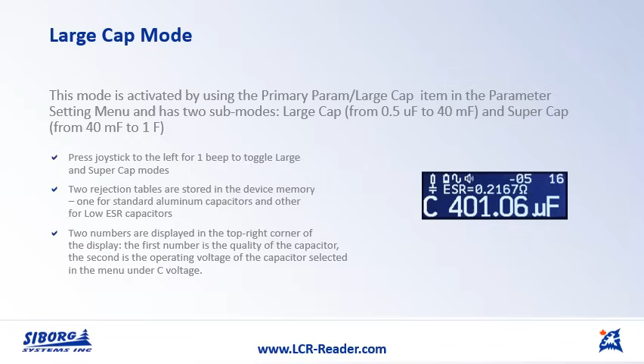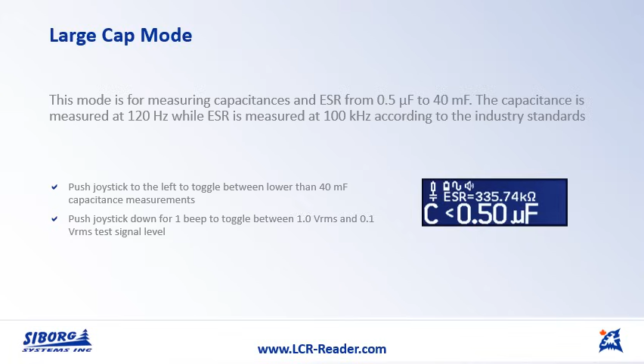Large cap mode. This mode is for measuring the capacitance or ESR from 0.5 microfarads to 40 millifarads. This capacitance is measured at 120 Hz, while ESR is measured at 100 kilohertz, according to the industry standards. If we push the joystick down for 1 beep, we toggle between the 1.0 Vrms and 0.1 Vrms test signal level.